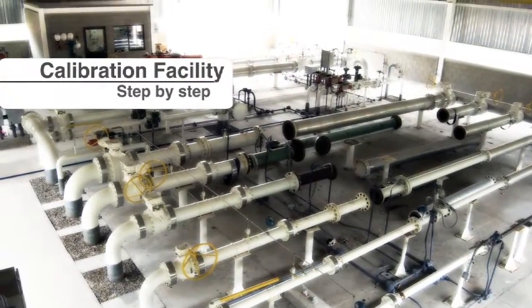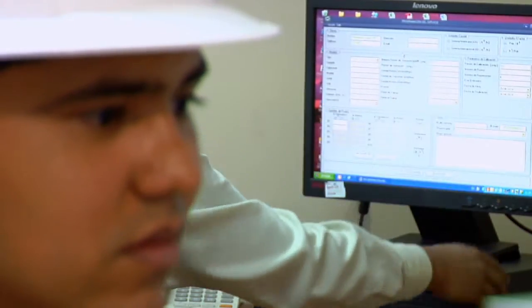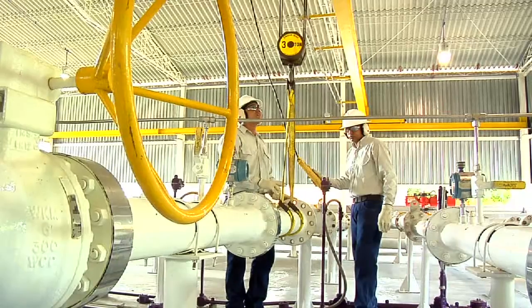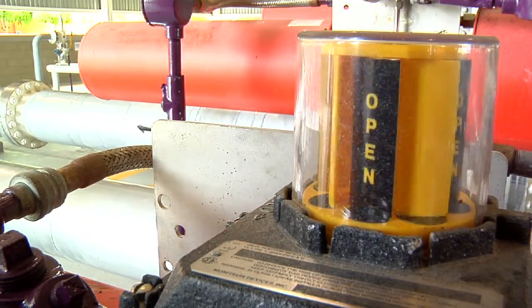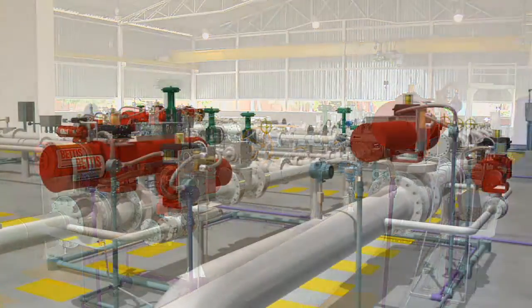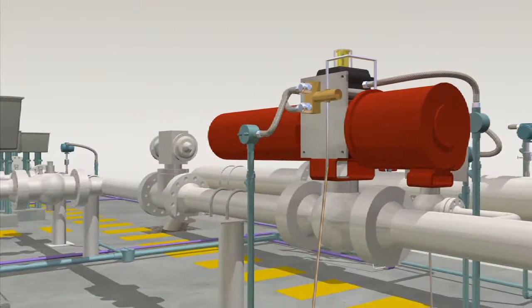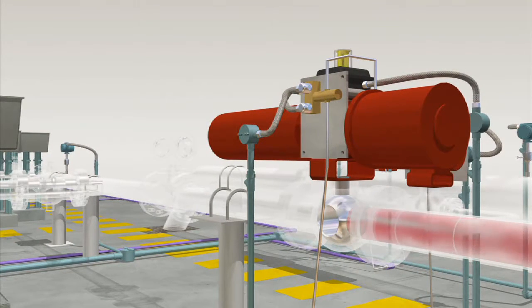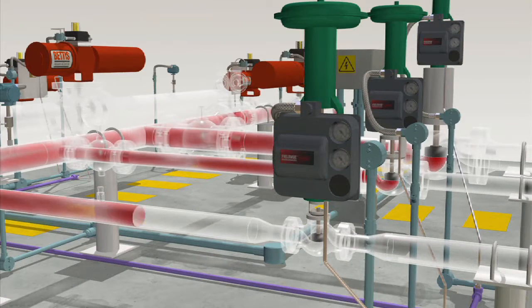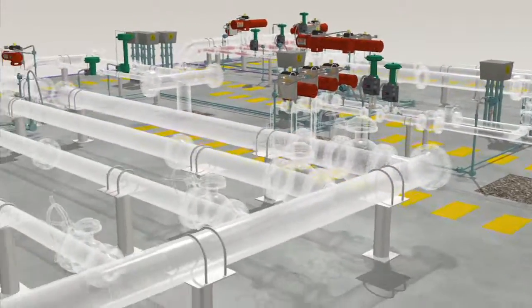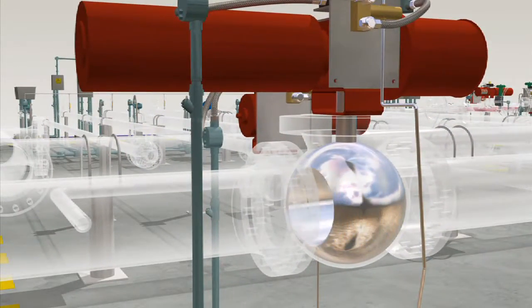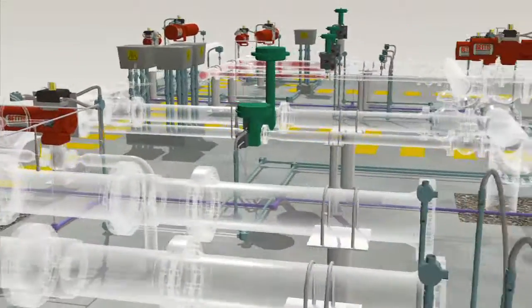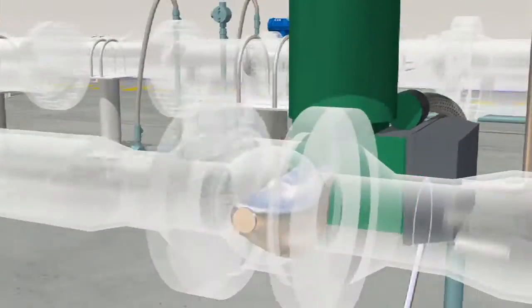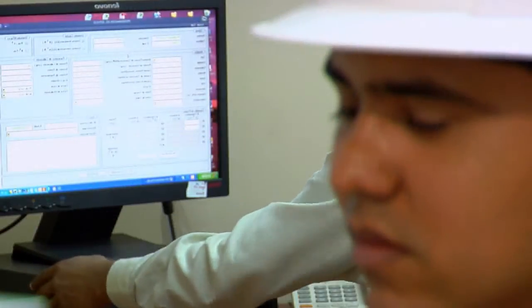How we operate. The process begins with configuration of the calibration software. This is done by a metrologist who enters information from the customer into the system, along with all the necessary parameters to begin the calibration. Initial pressurization consists of taking the gas pressure in the facility from 0 bar to 3.45 bar. This pressurization is automated and governed from the operation station and the main controller.